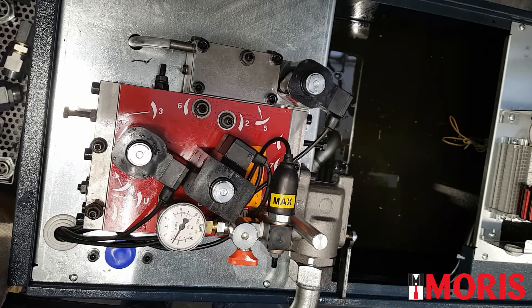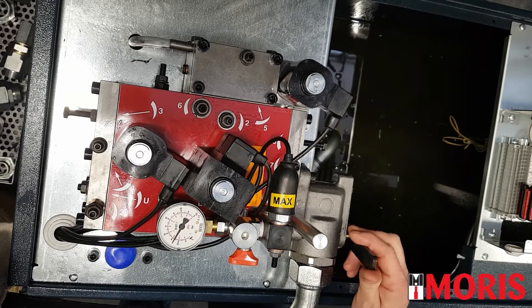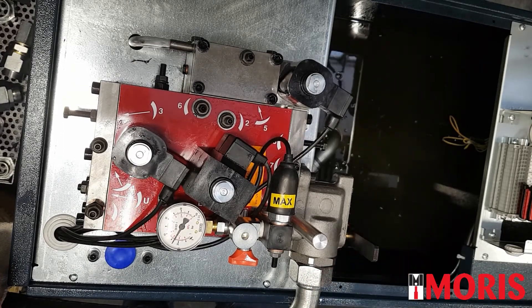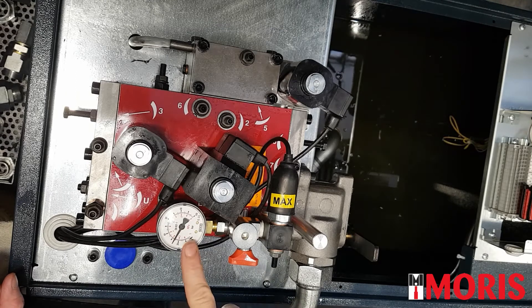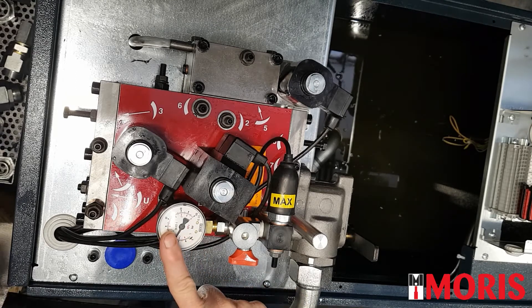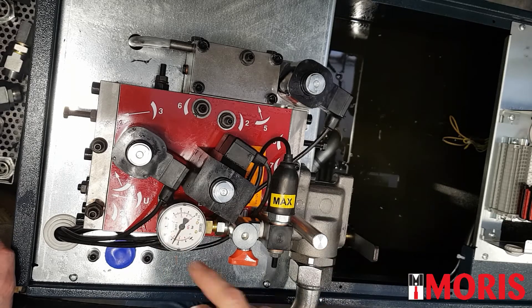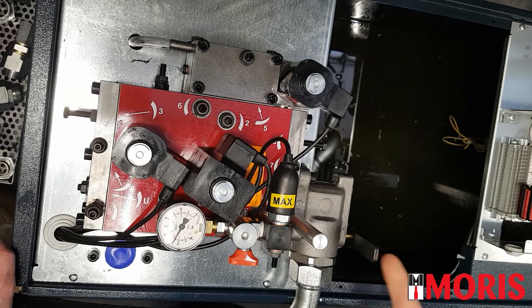Let's start with screw number 7. Close the ball valve, start the motor and at the same time look at the pressure gauge. If the needle moves in a smooth way, regulation number 7 is properly set. If the manometer is oscillating, then screw number 7 is too open.